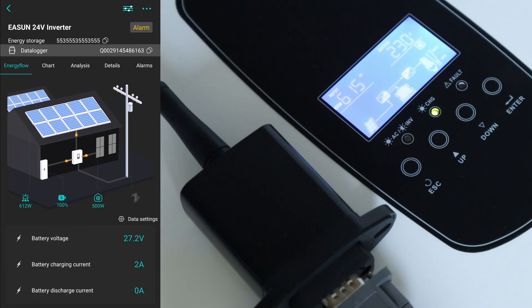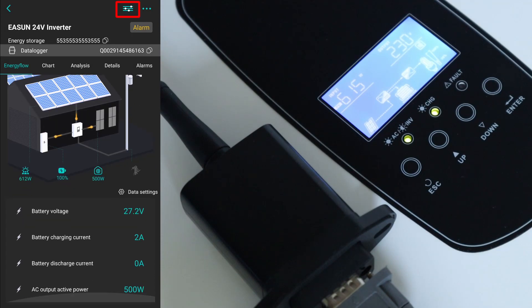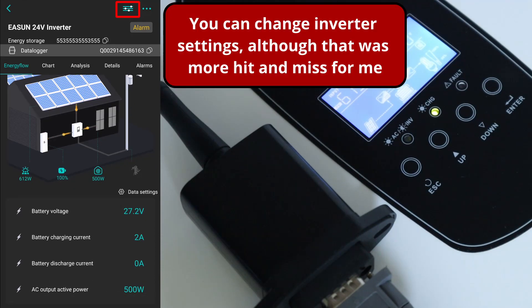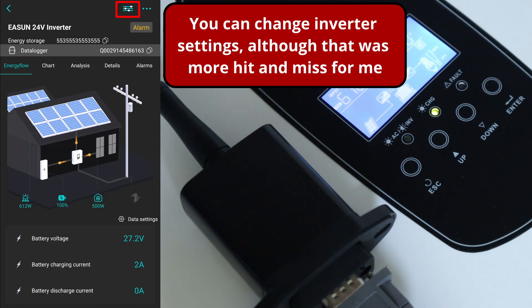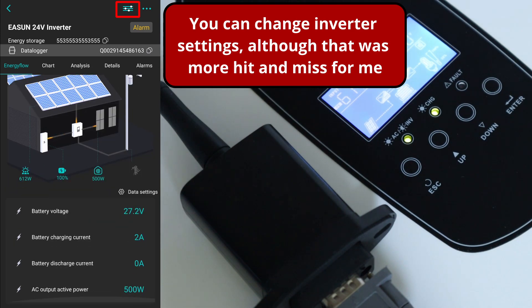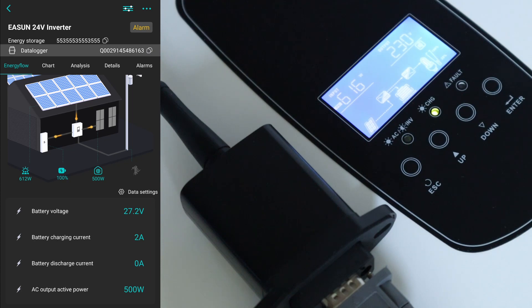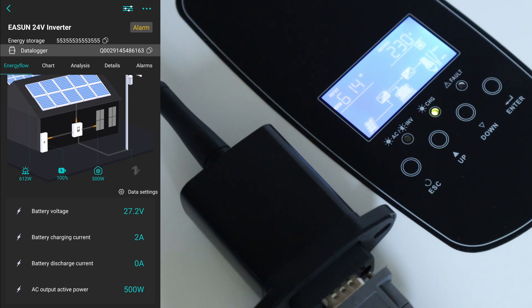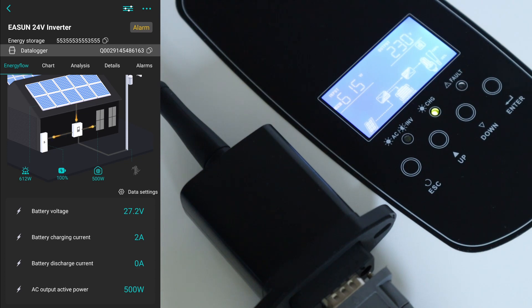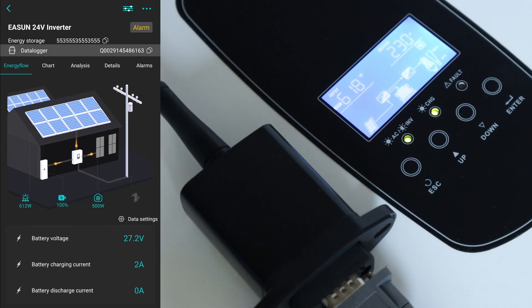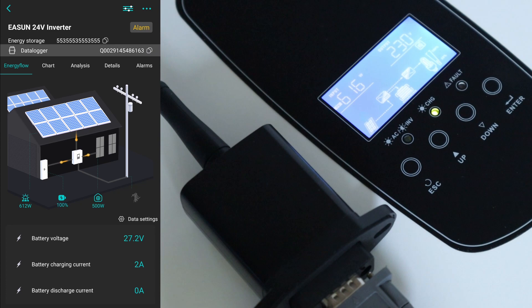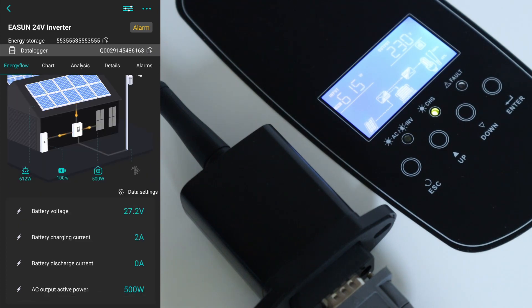So this is the primary page that you get, or the first view that you get, which is the energy flow. Now this isn't instantaneous, so this isn't real time - it's based on data that's captured via the WiFi dongle and then sent back up to the cloud. So the other thing on here you don't really want to take any notice of is the battery percentage, because again you need really a shunt to manage it and actually understand how much charge or how much capacity is actually held in there at any one time. So I pretty much ignore that.